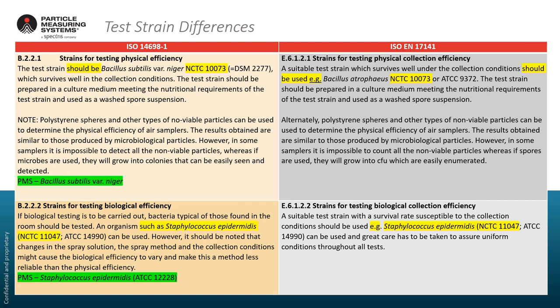The strains used for both tests are essentially the same, with a little language difference. ISO 14698 specifies Bacillus subtilis while EN 17141 uses language such as Bacillus, for example Bacillus atrophaeus, leaving some flexibility to pick something suitable that meets site requirements. In both instances, the test strains used by Particle Measuring Systems on their validation documents meet the specifications for both standards.